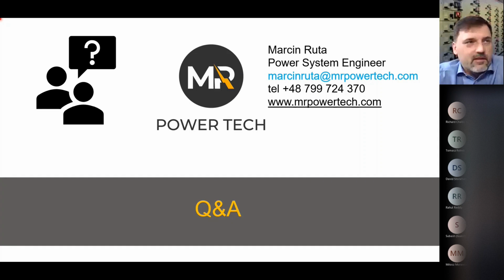Oh, we still have 5 minutes left. As a comment from my side, yeah, you can always use a light indicator. This way you know if your maintenance mode is activated or not while entering the switch room. Again, it depends how it's designed. I recommend having lockout, tagout, and a clear switch on off, so you see the position. You don't have to do it on the breaker. You might, but you don't have to. And as Jerome said, you might also have a clear light saying, yeah, it's activated. So I hope it explains.